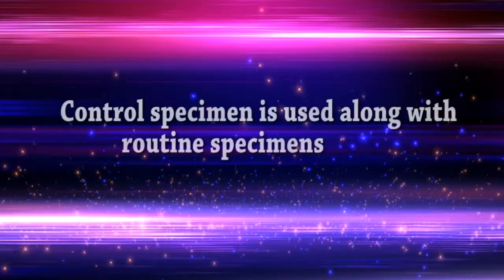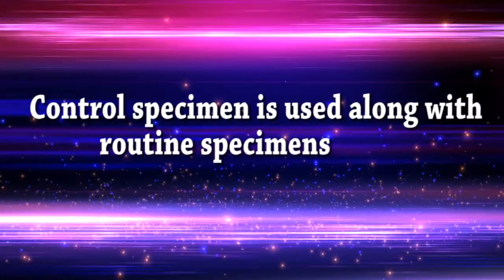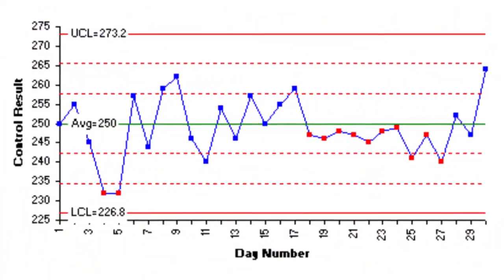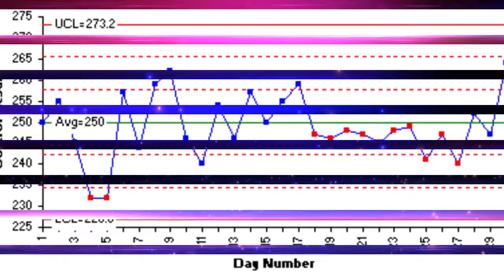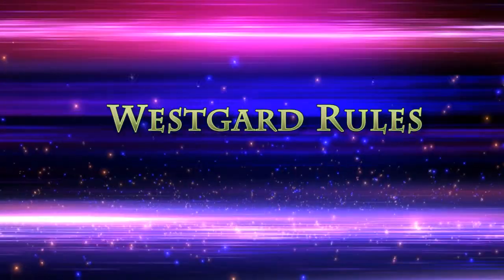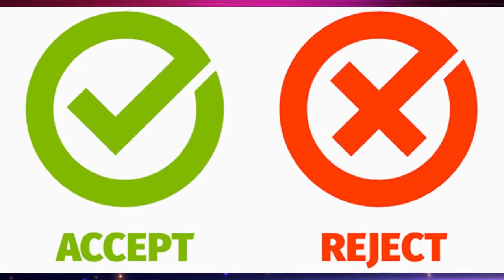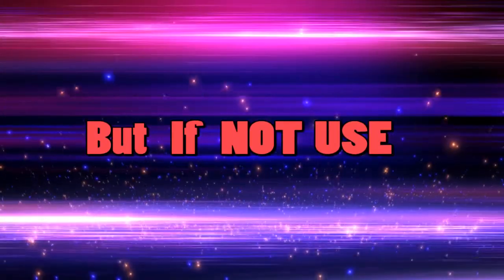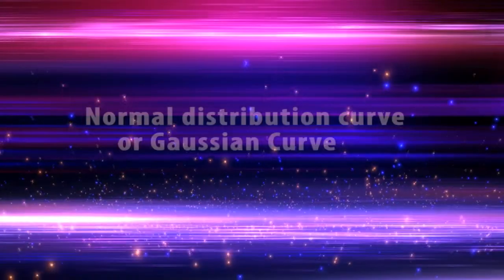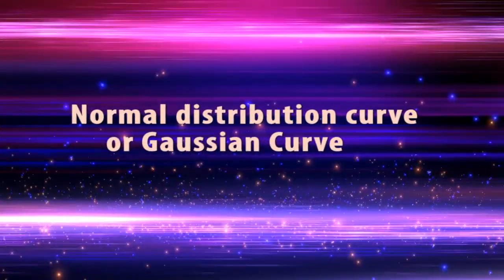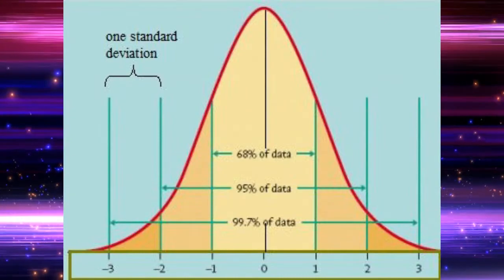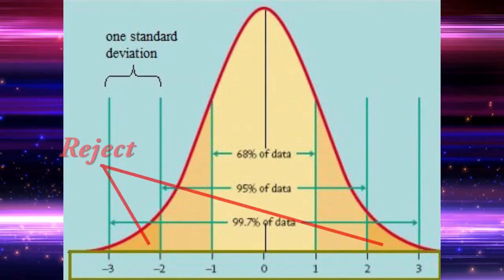Subsequently, the control specimen is used along with routine specimens and plotted on a chart called the Levey-Jennings chart. The Westgard rules are applied to accept or reject results. If Westgard rules are not used, one has to use a normal distribution curve or Gaussian curve.